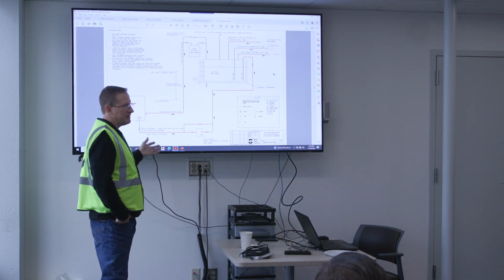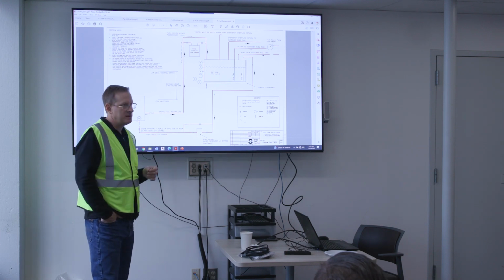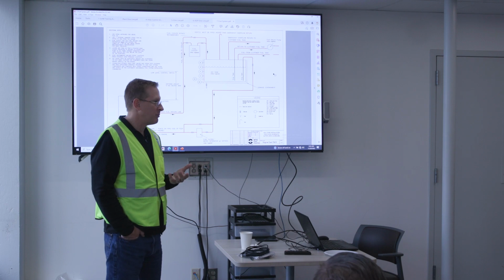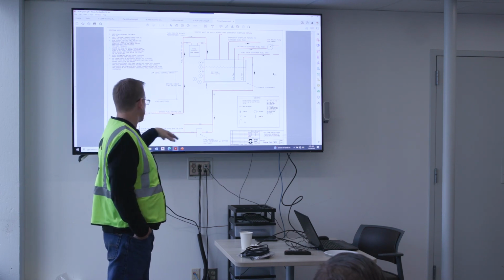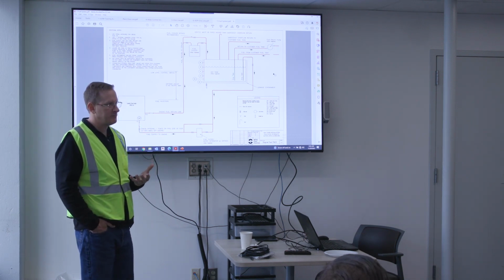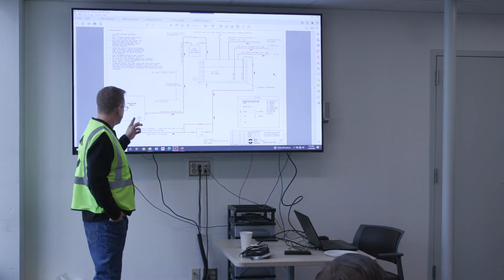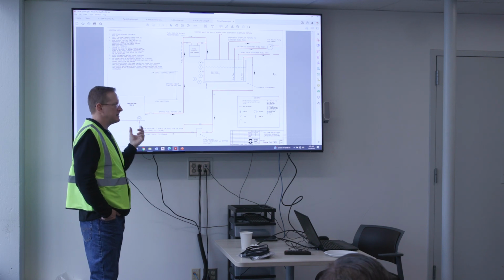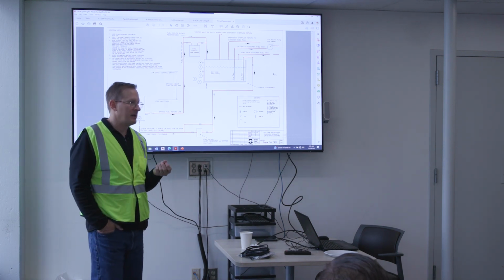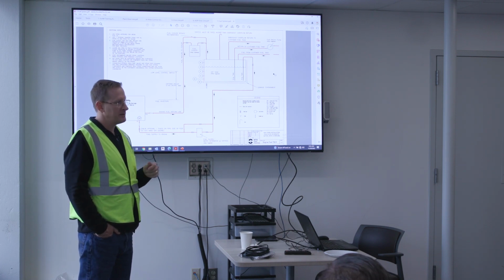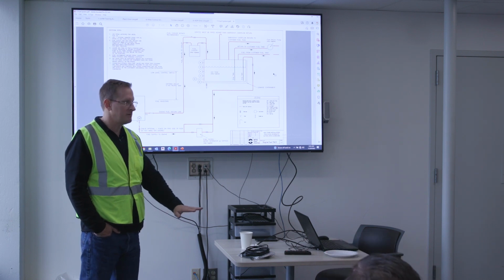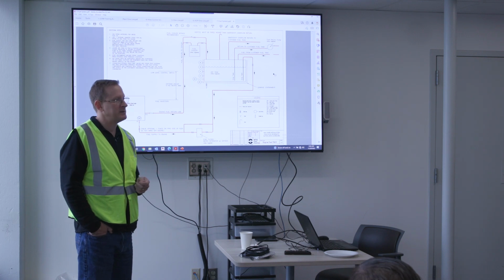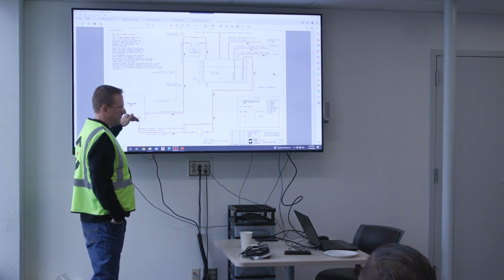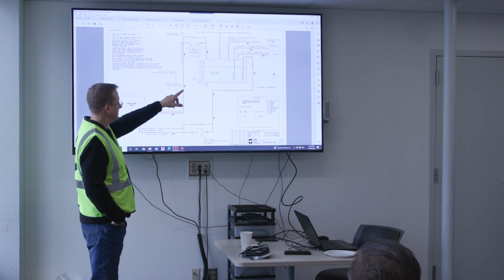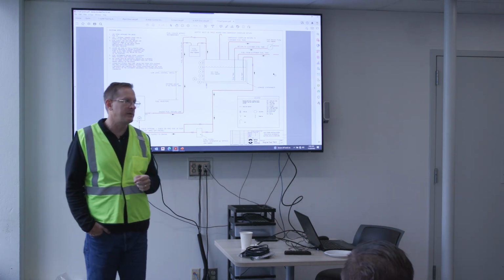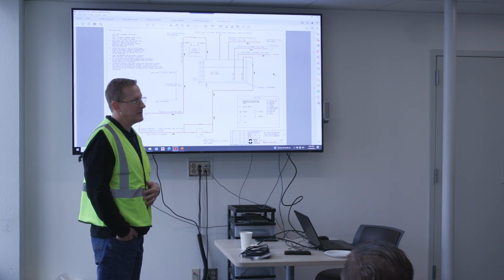We won't typically lose prime, and even when we introduce fuel into the engine from the get-go, it's not often that we need to actually prime the system, because the gravity feed is usually enough to where it can draw fuel into the engine without having to do an external priming pump operation. Now, the fuel filter on the engine itself, the one that's attached to the front, actually has a lift pump to it. So it'll actually help the prime as well. If you were to draw fuel from the bottom of the engine, which is what most gen sets might do, that lift pump would help that situation and keep it primed. So it's really more of a backup priming system that is on that engine. But with the raised day tank, there's not a whole lot of priming that you have to do externally, even when you're changing filters or having to drain the system for whatever reason.